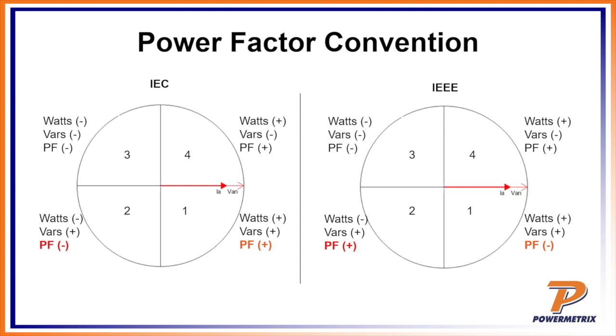So again, the customer called me and asked, why do I see a negative power factor on my Power Master, but a positive power factor on my meter? And that's why, because of the way the meter's been programmed. So be very, very clear when you do your programming to find out which power factor convention the meter is actually using. Luckily, the vast majority I've seen are using the IEC convention, so we should be good, but this one particular meter was using the IEEE, and it's the only one they were using.